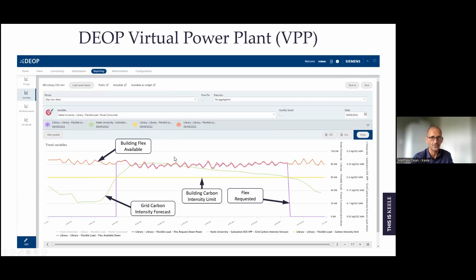As soon as we breach that carbon intensity limit, and for that duration there, we start calling off the maximum available flex in that building, basically trying to turn down as many assets as we can while the grid is at its dirtiest.